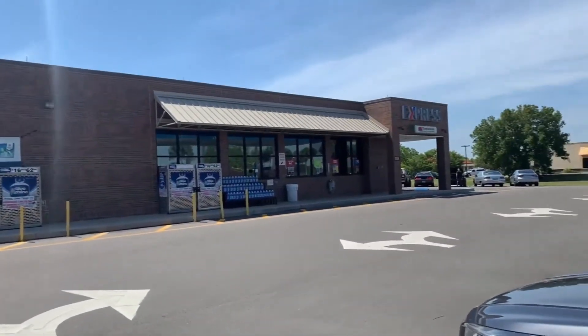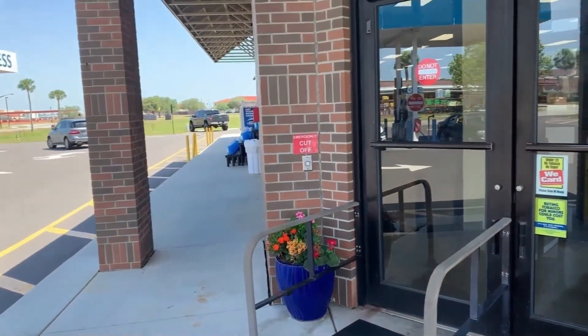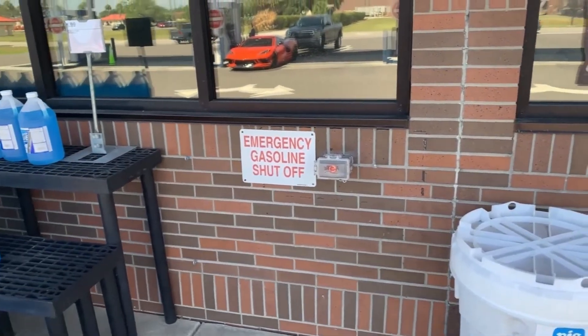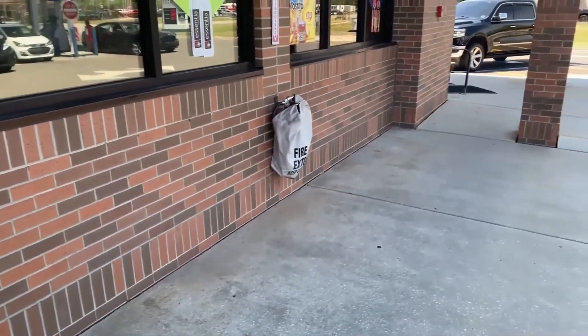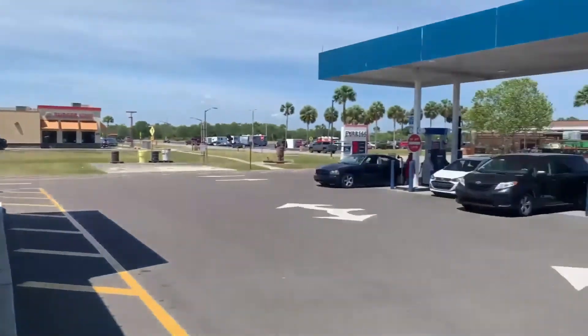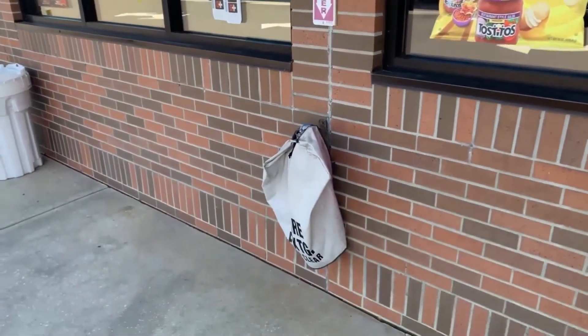You can see the cutoffs really well here — emergency cutoff at the door. Another emergency shutoff with a very good sign and a spill kit readily available, close to the fire extinguisher, with other cutoff switches right around the corner. Dispensers are right here. Fire extinguisher is labeled.